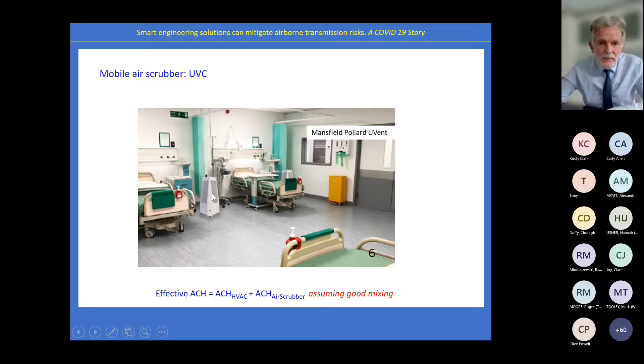This one has been on the market for a while and is very popular with dentists on the high street. But look at this: it clears a 45 cubic meter room in 1.3 minutes. I know the company, they're good, the engineering is good, but isn't this absolutely useless science? Clearance to what level — 5%, 10%, 99%? This is very typical of kit that's appeared on the market in the last 2.5 years, very quickly, without good governance of how it's delivered.